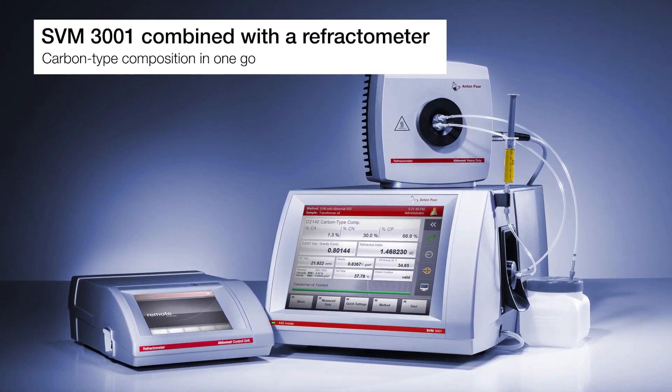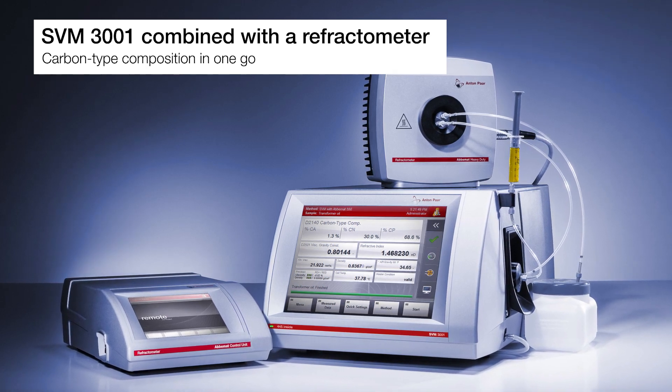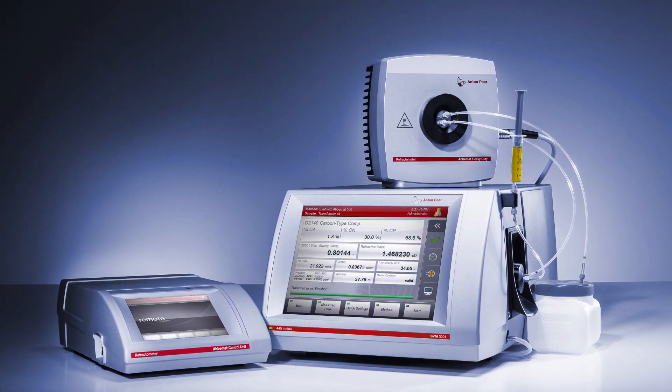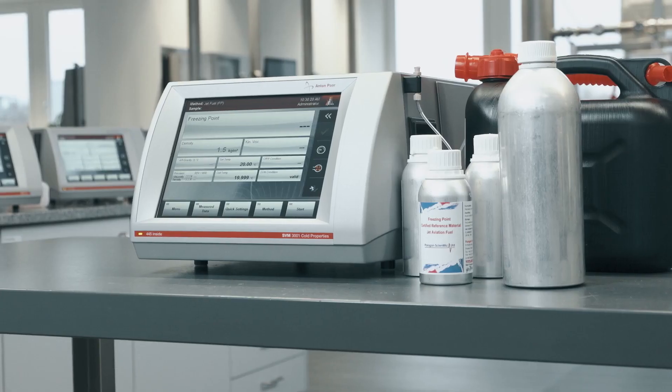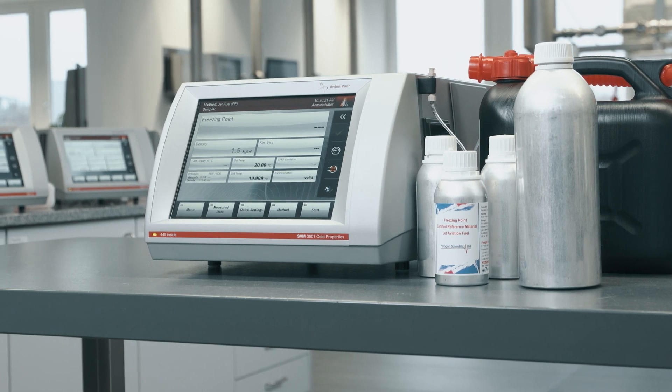With SVM 3001 in combination with an Anton Paar refractometer, one fast measurement yields the carbon-type composition of transformer oils. For low temperature applications, SVM 3001 cold properties is your all-in-one solution.